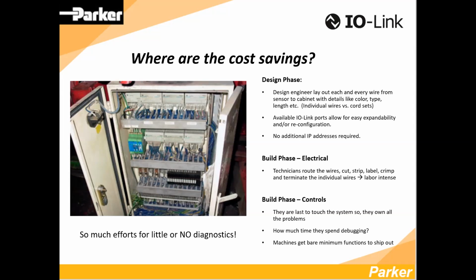And with IOLink, it's from one end to the other. In the design phase, normally when you're laying out electricals, if you're doing hard wiring, every conductor you have to label, you have to route, you have to land. With IOLink, you're using molded cables. So basically you're taking 4 or 5 conductors that you would have labeled individually, routed individually, landed on a terminal strip, whatever it may be, and now it's just a cable definition.